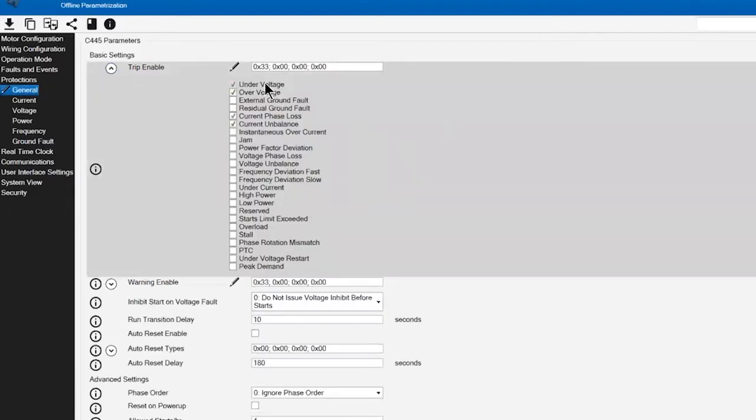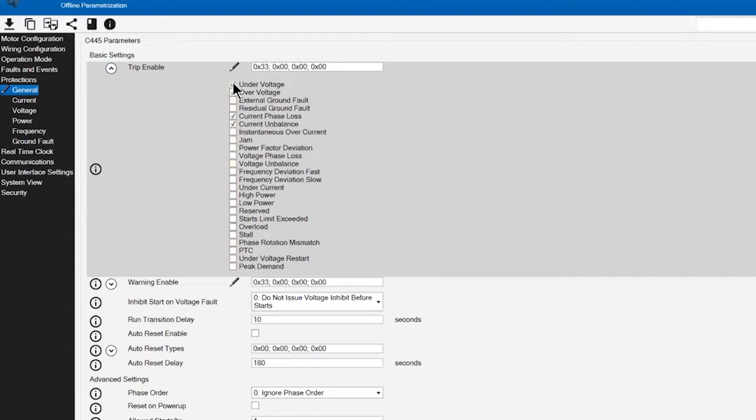The way they have developed the software, it's real straightforward. We have a list here under the trip enable of all the different protective functions included within this motor management relay, and simply by clicking on a specific protection will enable that protection. As we walk through this configuration, we'll be able to set the limits and delays associated with those.